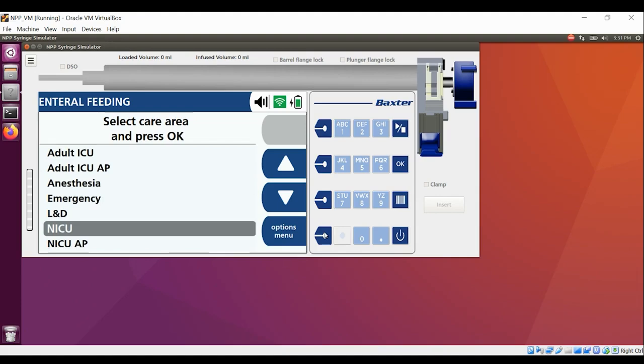Now, the prime feature is very critical when you're delivering very critical meds at very, very low rates. Because as you can imagine, when you're delivering at 0.1 ml an hour, it would be a long time for that medication to get to the patient if you haven't removed that mechanical slack and cinched up those gears. Reminder that some clinicians in the NICU care area may use double pumping for the reduction of mechanical slack and to improve that startup time. And as we discussed a while ago in our training, double pumping is getting a second pump started and running for several minutes to even longer, an hour or so, just to make sure that there's a nice continuous flow when they do attach to the patient.